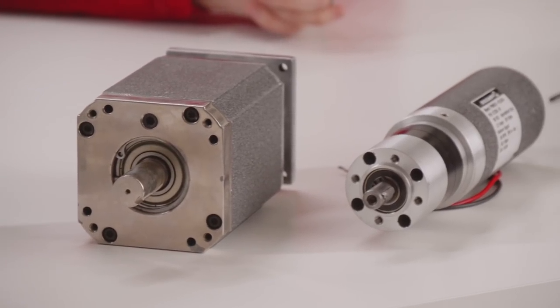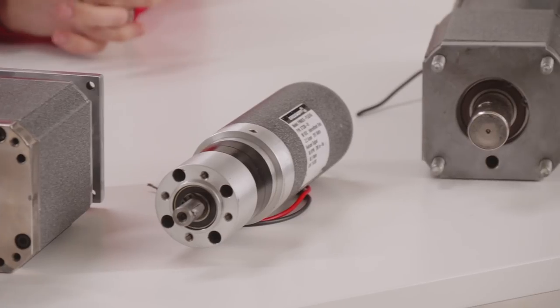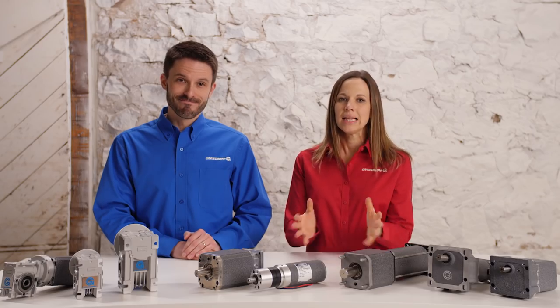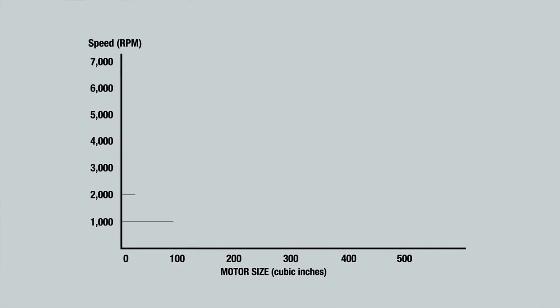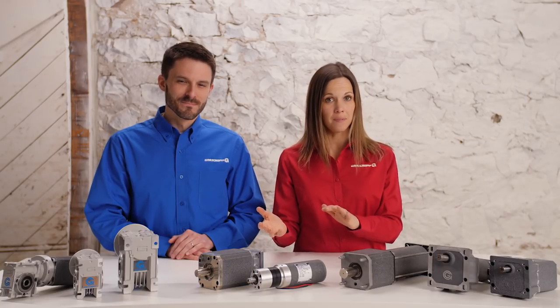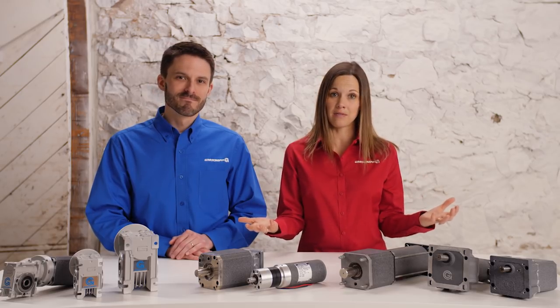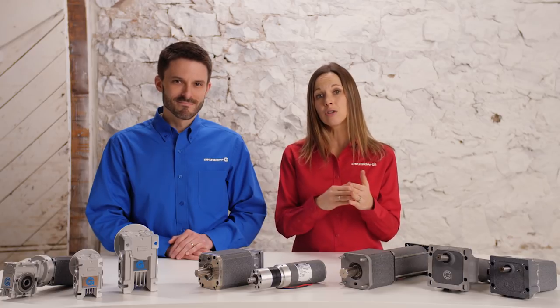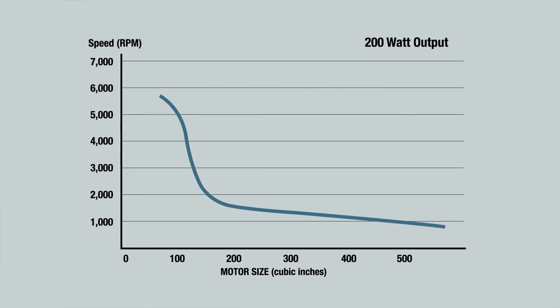Once the motor is selected, you'll need to consider the motor size versus its relationship to the desired speed and output torque, as this influences reducer selection. We've graphed the speed in RPM required for a range of different motor sizes to achieve an output of 200 watts. As you can see, you would need a roughly 500 cubic inch motor at 1,000 RPM to achieve 200 watts of output. Imagine the size motor you would need to run at 100 RPM — it would be the size of a house. Basically, the slower the motor speed, the larger the motor needs to be. Large motors can be expensive and may not fit the envelope specified for an application. The alternative is to pair a gear reducer with a smaller motor. The sweet spot on the curve is where motor size versus speed is optimized, and using a gearbox enables the smaller motor to operate in that zone.